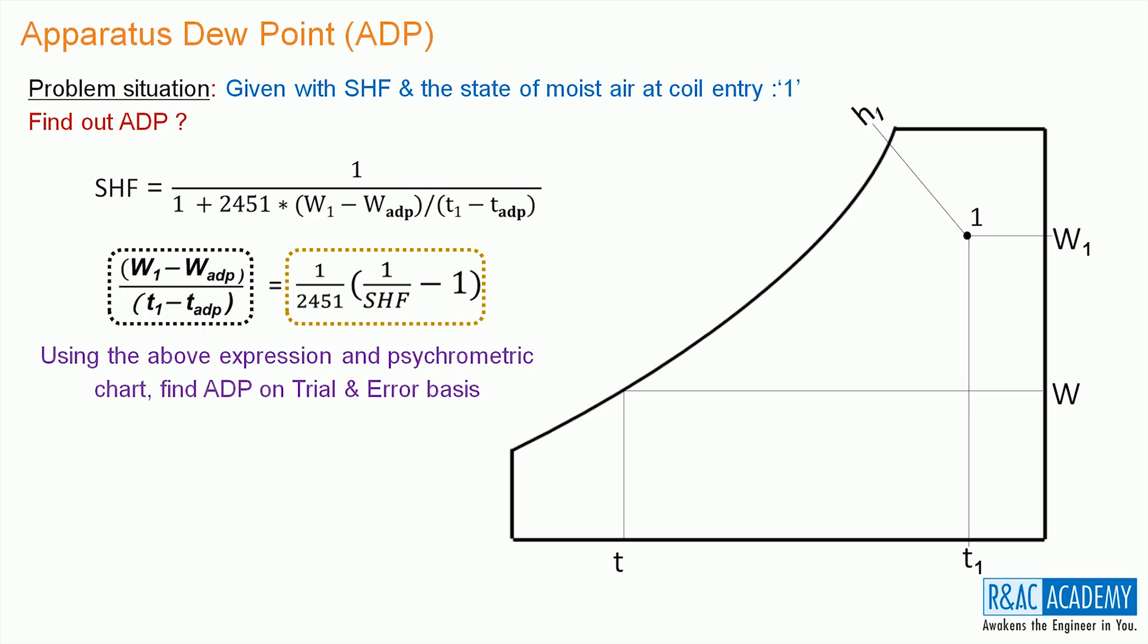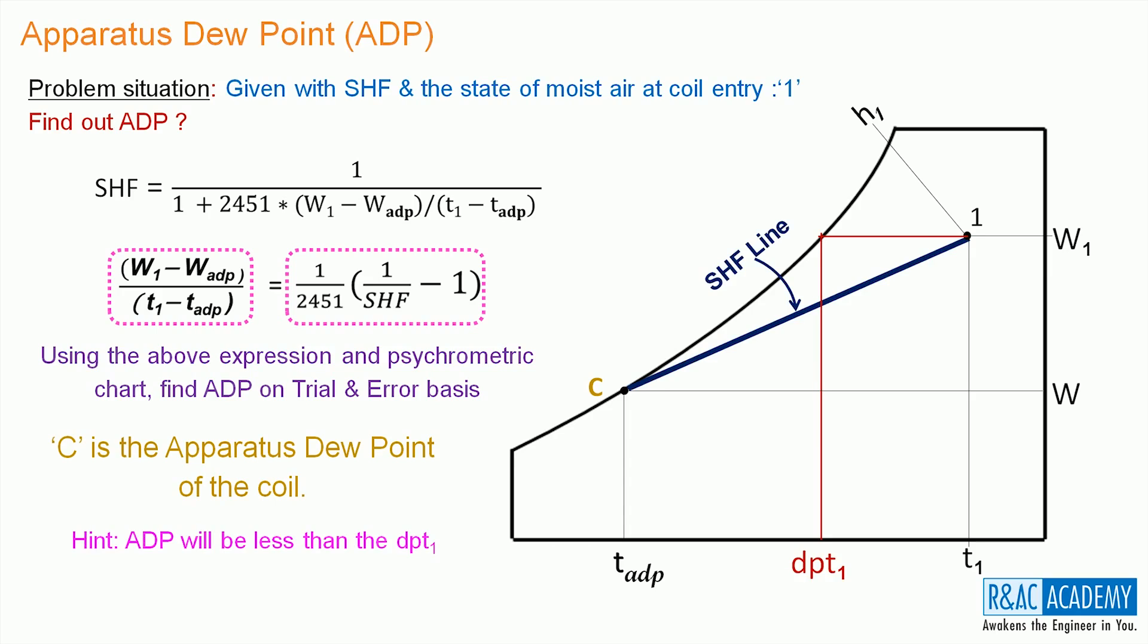If not, change the T value accordingly, collect the corresponding W value from the chart and repeat the process. Whenever the LHS value becomes equal to the RHS value, that temperature is the TADP, that is apparatus dew point temperature. The point C is the coil ADP and this is the sensible heat factor line. A small hint here: ADP will always be less than the dew point temperature of the air at the coil entry.